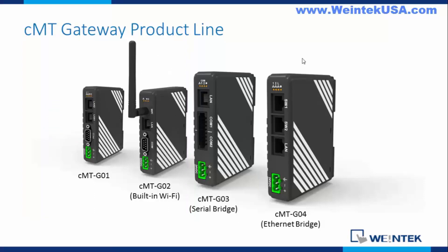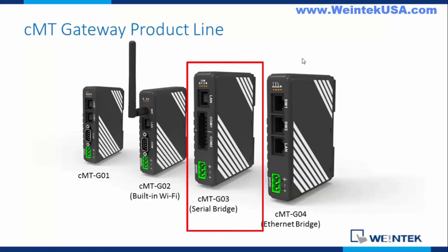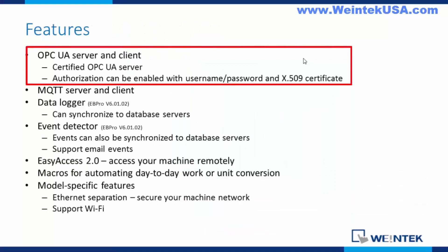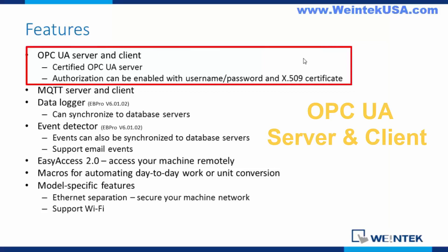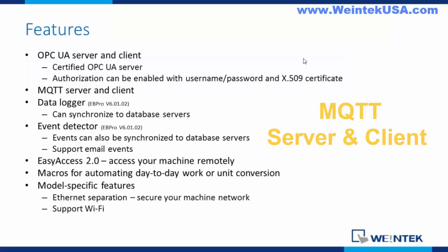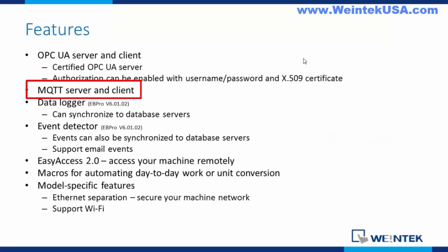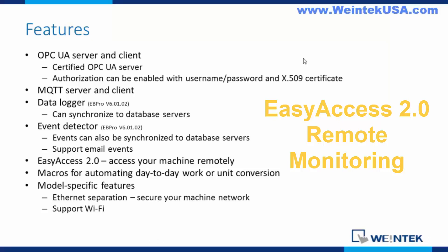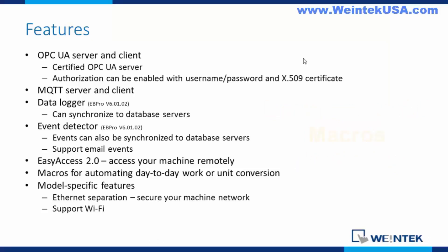We are now adding the cMT-G03, our serial bridge solution, and the cMT-G04, which is the Ethernet bridge solution. The CMT G0 series are certified OPC UA servers — they can be an OPC UA server, client, or both. They can also be an MQTT server or client. They support full data logging capabilities that can be synchronized to database servers, as well as events. Easy Access 2.0 lets you monitor any of that remotely.